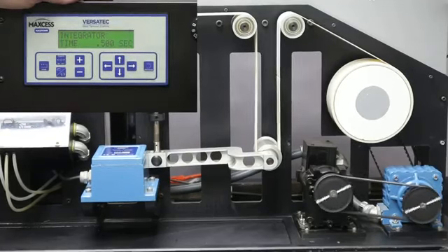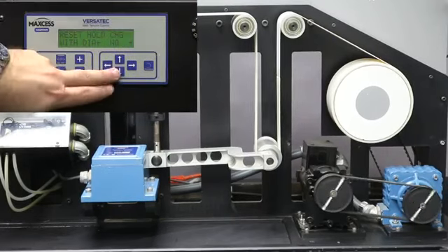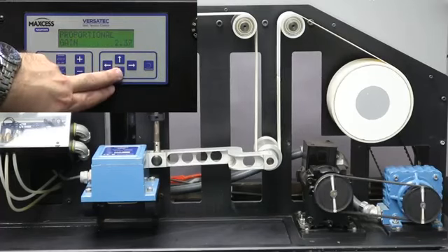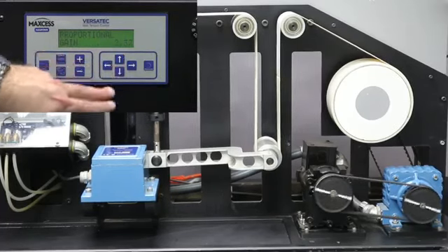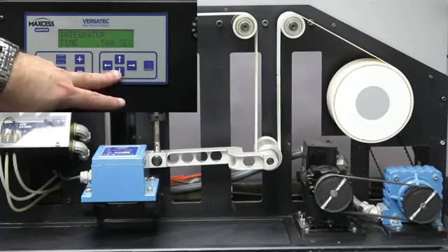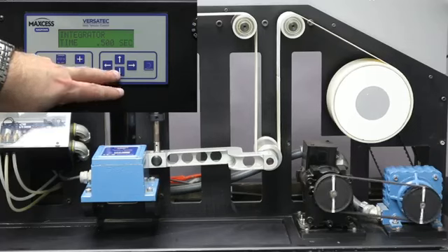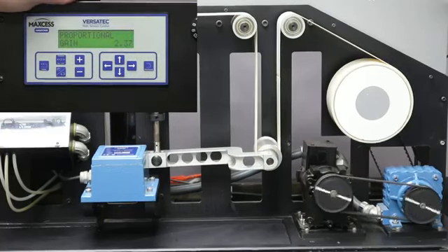We talked about the different features and things that you can add to it, like the sensors and the current to pressure transducer and the gain scheduling. We're not demoing all of that stuff right now, but I do have direct access to the integrator, the proportional gain, and the derivative. So you can see right now, my integrator ended up at 1/2 second, so it's going out and looking for an error every 1/2 second. Our proportional gain ended up at 2.37.